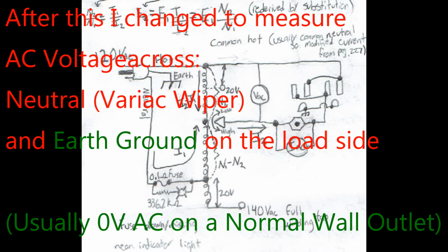The measurements that were just discussed were probably taken by the original engineer who wired this, but they probably didn't go the next step to actually measure the AC voltage across the neutral, which is the Variac wiper in this case, and the earth ground on the load side. Normally this is really close to 0 volts AC on a normal wall outlet, but as we can show, we can actually get this to change all the way up to 120 volts maximum.